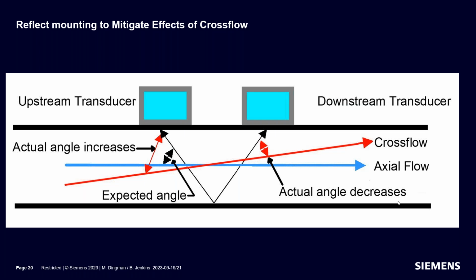Reflect mounting not only gives you better averaging of the flow stream because the sonic beam spends twice as much time in the flow stream, but it gives you that reverse angle correction, and that will cancel out effects of crossflow. So combined with multiple paths, reflect mounting, and the flow profile tool, you can significantly minimize or eliminate the effects of limited straight run of piping.